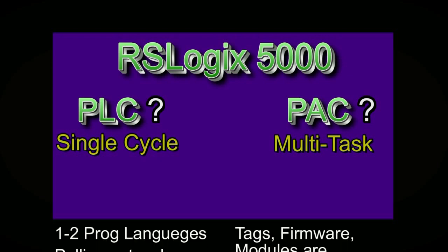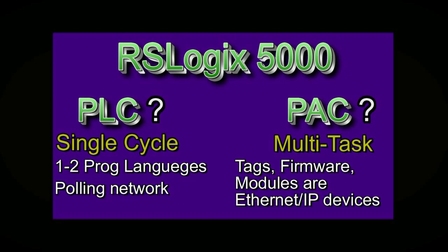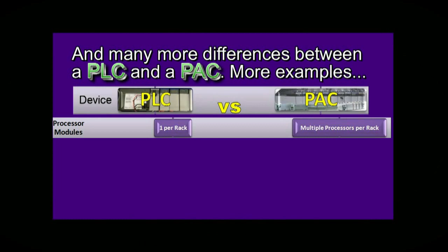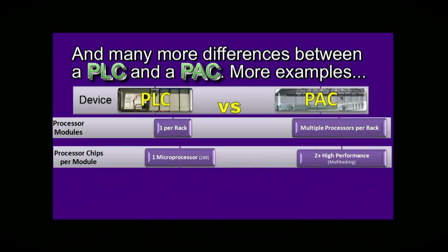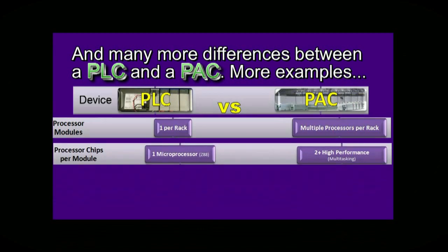A PAC has additional differences to the PLC too, like motion control, tags, firmware, etc. There are many more differences, some of which are listed here. A PLC can only have one processor module in the first slot, whereas a PAC can have multiple modules in any slot, as they are just Ethernet devices on a network.